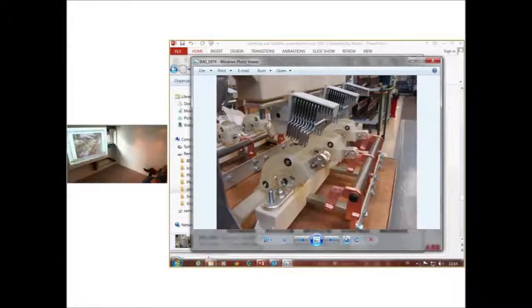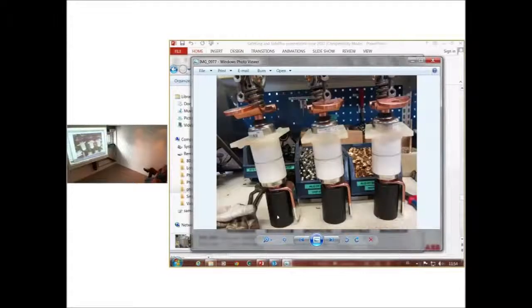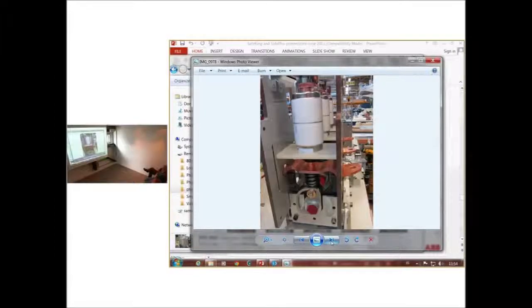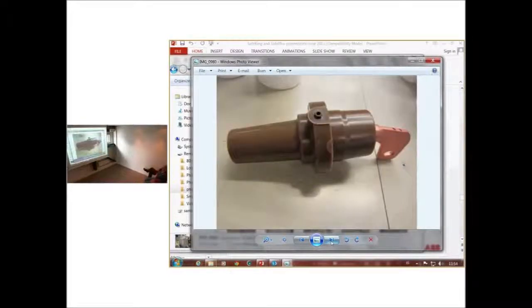These switches will then be put into the vacuum circuit bottles, and they will then be put into a rack. And this rack will be put in, and then the bushing. And the bushing is important, because on this bushing there is a pickup point.